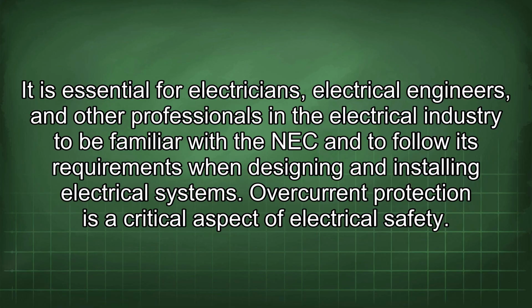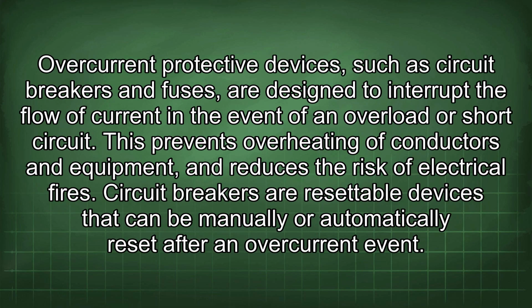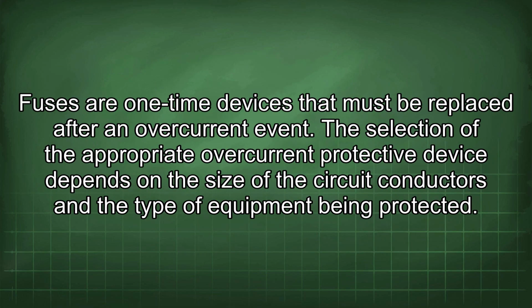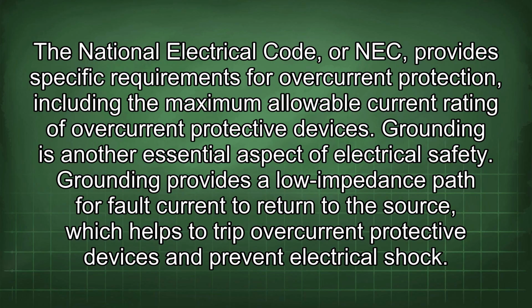Overcurrent protection is a critical aspect of electrical safety. Overcurrent protective devices such as circuit breakers and fuses are designed to interrupt the flow of current in the event of an overload or short circuit. This prevents overheating of conductors and equipment and reduces the risk of electrical fires. Circuit breakers are resettable devices that can be manually or automatically reset after an overcurrent event. Fuses are one-time devices that must be replaced after an overcurrent event. The selection of the appropriate overcurrent protective device depends on the size of the circuit conductors and the type of equipment being protected. The National Electrical Code, or NEC, provides specific requirements for overcurrent protection, including the maximum allowable current rating of overcurrent protective devices.